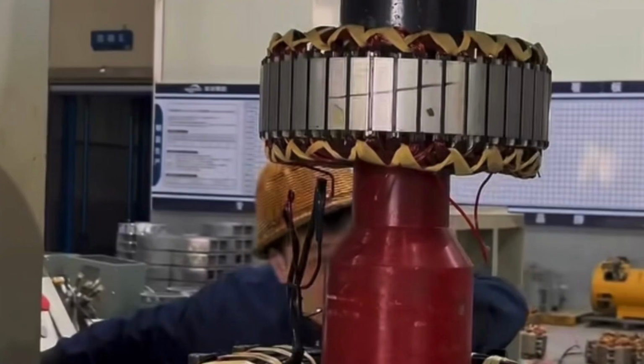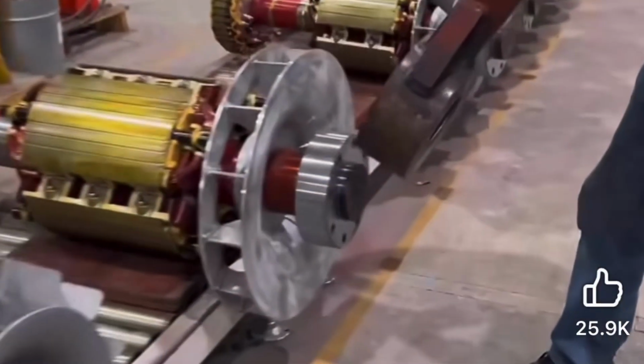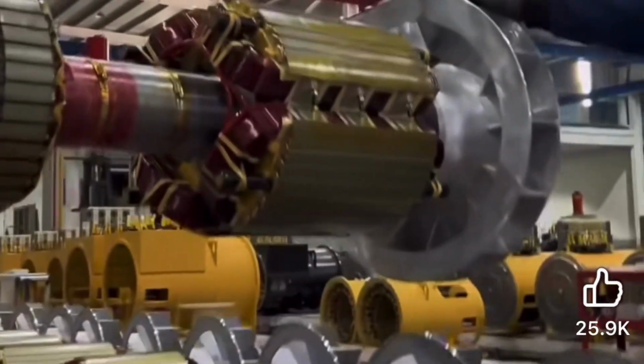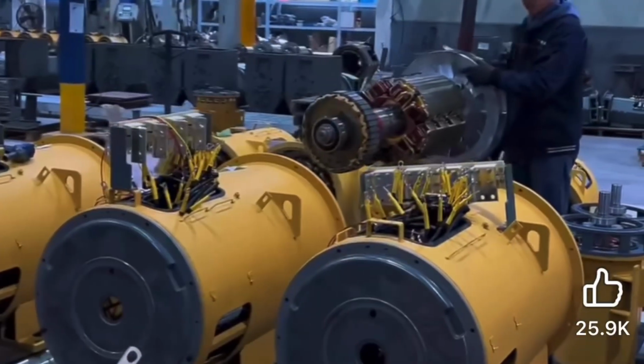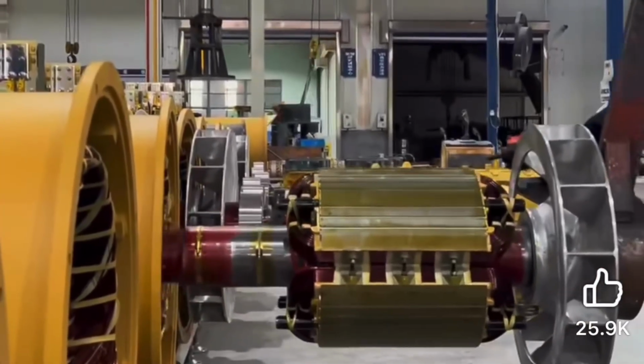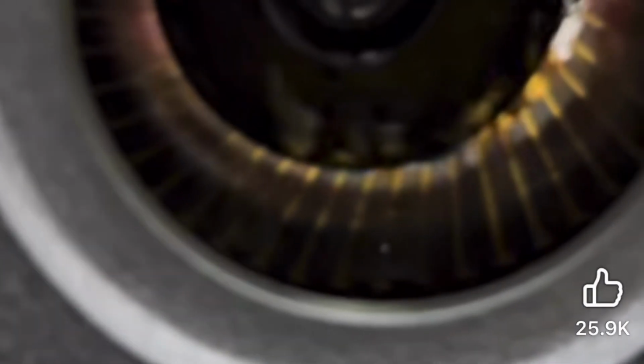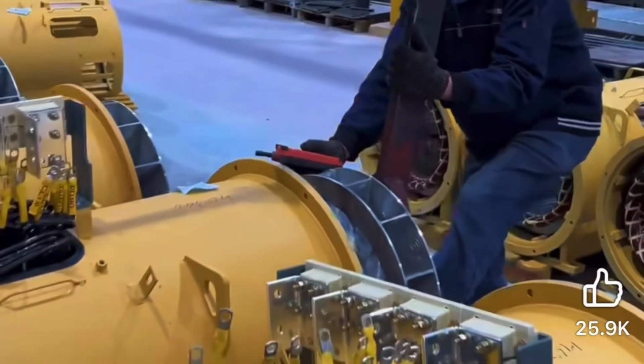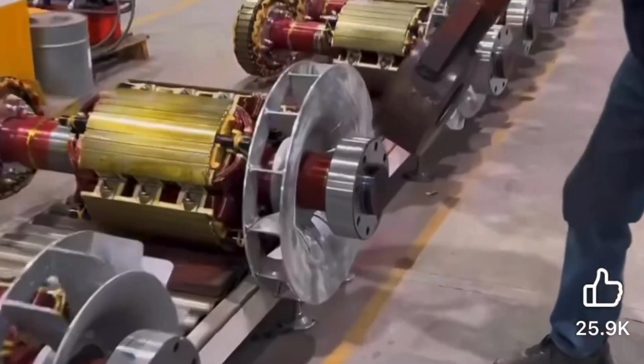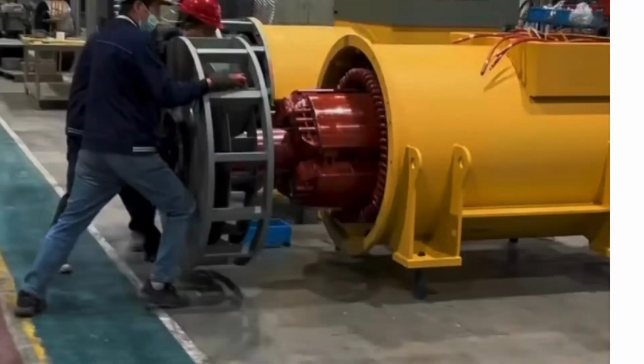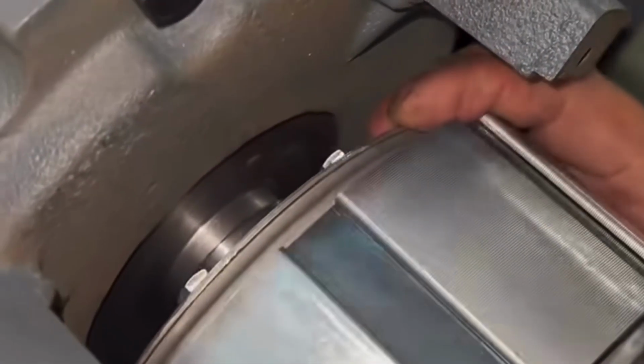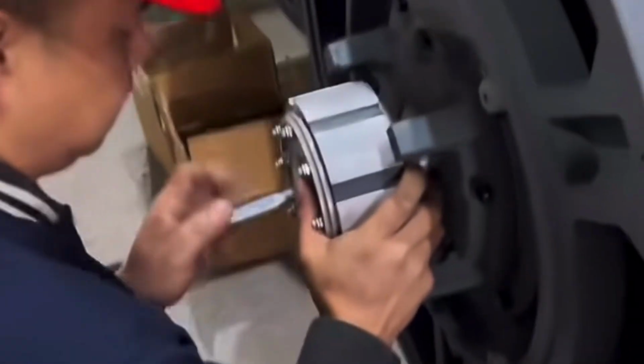The next step involves the installation of the excitation winding system. This system is responsible for generating the magnetic field required for electricity production. High-quality insulated windings are connected and tested to ensure stable and controlled excitation during operation. In advanced systems, a permanent magnet generator, or PMG, is also integrated. The PMG provides an independent power source for the excitation system, improving voltage stability and ensuring reliable startup performance, even under varying load conditions.